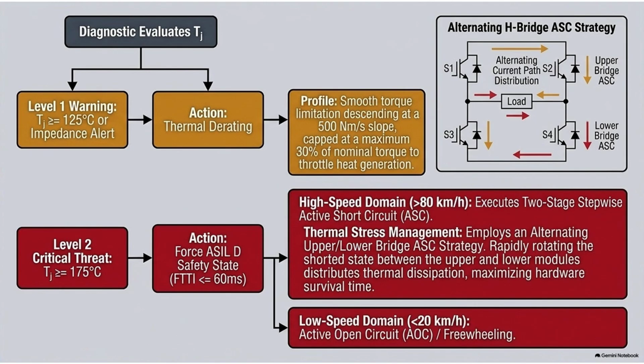That is incredibly clever. But here's where things get really deep, and where I actually thought I found a massive flaw in the engineering logic. Oh, let's hear it. I was reading the documentation, and it explicitly notes that these physical NTC sensors have a thermal conduction lag of 50 to 200 milliseconds. Yes, the thermal time constant. Right. Meaning, from the exact millisecond the silicon chip actually gets dangerously hot, to the moment that heat physically travels through the copper substrate, warms up the casing of the NTC sensor, and registers a voltage change in the computer, up to a fifth of a second has passed.